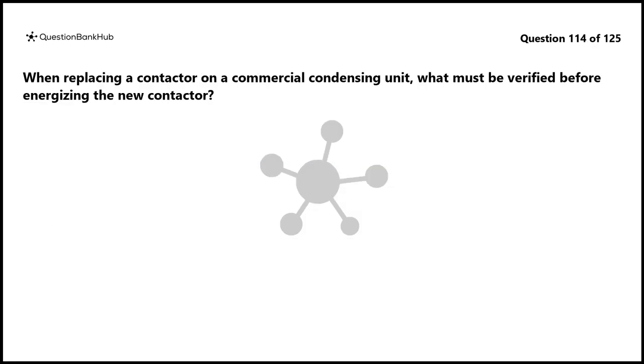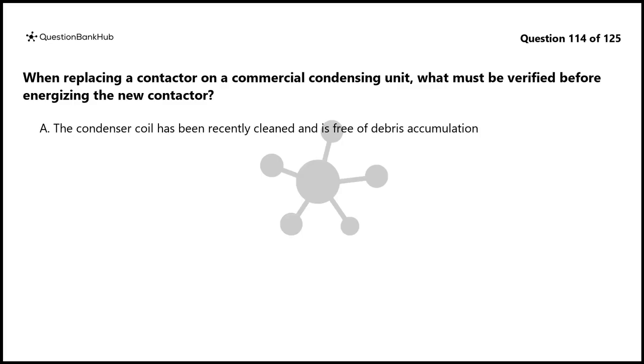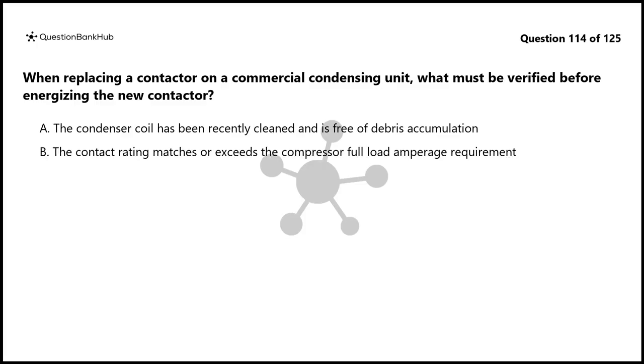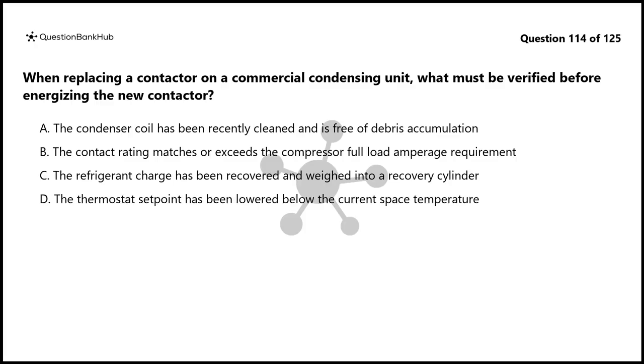Question 114. When replacing a contactor on a commercial condensing unit, what must be verified before energizing the new contactor? A. The condenser coil has been recently cleaned and is free of debris accumulation. B. The contact rating matches or exceeds the compressor full load amperage requirement. C. The refrigerant charge has been recovered and weighed into a recovery cylinder. D. The thermostat setpoint has been lowered below the current space temperature.